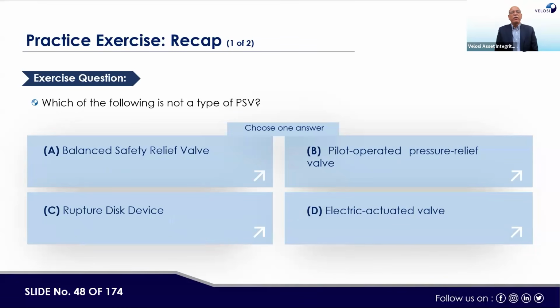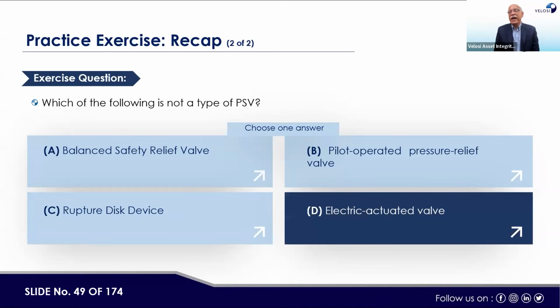So now, which of the following valve types is not a PSV? Which of the following is not a type of PSV? A, the balance safety relief valve. B, pilot operated pressure relief valve. C, the rupture disc device. D, electrical actuated valve. Which one? The answer again is D. Electric actuated valves are not part of the PSV valve, because PSVs are mechanically operated valves on a set point basis.